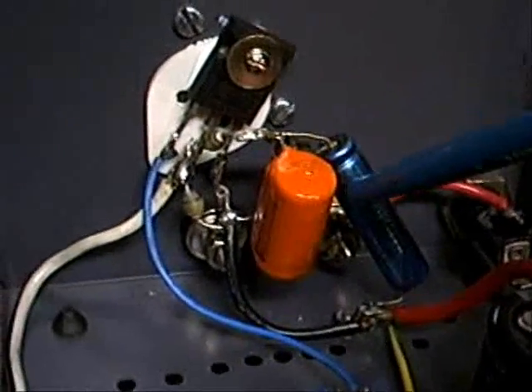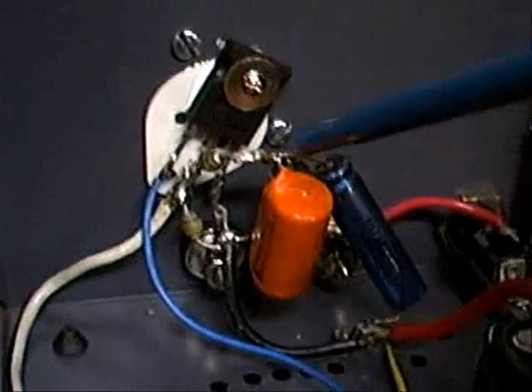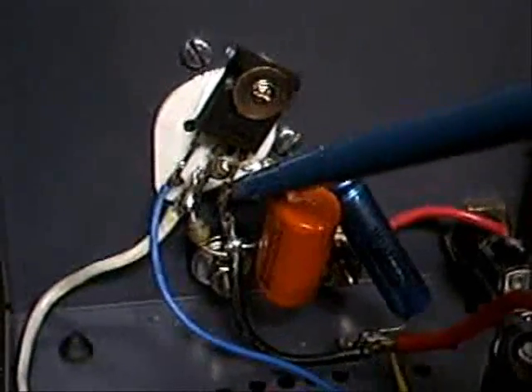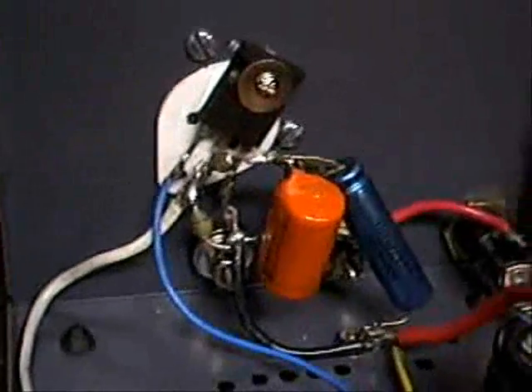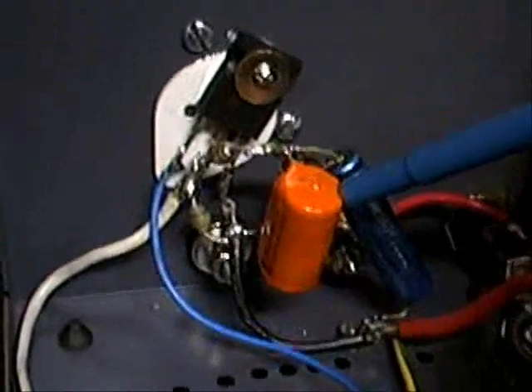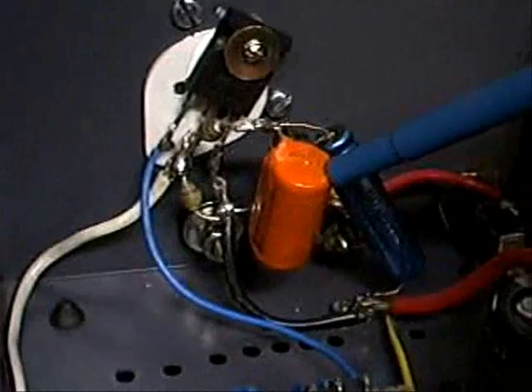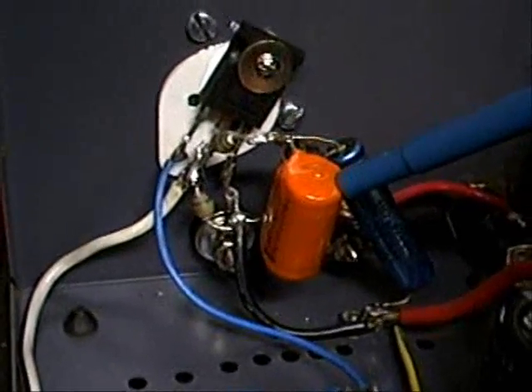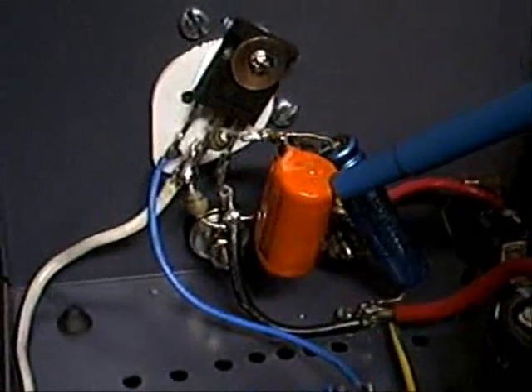This is so that the average DC voltage level will rise to a point just above where we want the transient voltage suppression, the positive transient voltage suppression rectifier to clip any positive transients. The 0.1 microfarad polystyrene capacitor enhances the high frequency bleed off of the transients to ground.